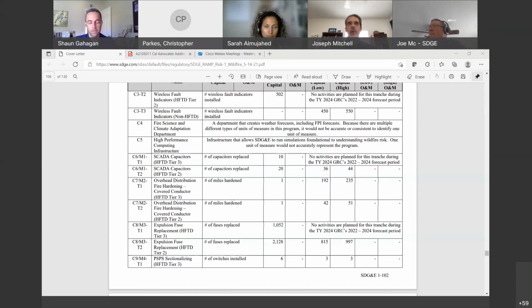So that's more of a repair program. Are you targeting mostly copper wire circuits for replacement, and not ACSR? Correct, the copper wire was originally the known conductor type with a larger failure rate than the aluminum conductors.